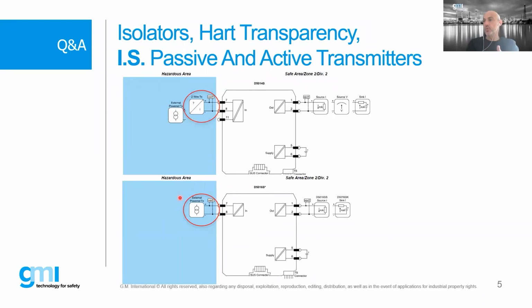That's why we developed a new unit that is supporting the HART protocol when the transmitter is already powered by an external source. So in this case, the loop is active, and this unit transfers the HART protocol also for this kind of transmitters. So if you have passive transmitters, you use these modules. If you have active transmitters, use these modules. Maybe we can be more clear, or you can look at the manuals for more details.